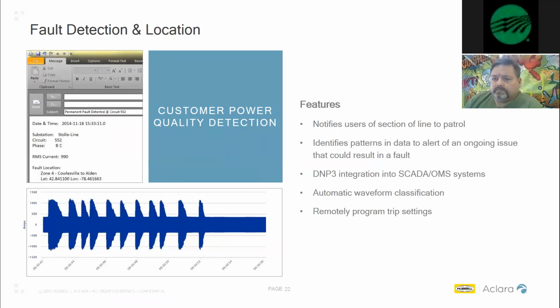Fault detection and location. Okay, so this is a really important one for me to go through with you. Using the sensors that are installed throughout your network, you obviously want to know where faults are occurring, where outages are occurring, and how do I do that? How does the system help me do that without manually driving a truck and having to patrol these lines manually? The Aclara grid monitoring system uses 2 different ways to detect these types of faults. We use a circuit segmentation method, which, as you can figure out pretty simply, means that if you're installing on a feeder, you have 3 sets of sensors. When those sensors are involved in a certain event or a disturbance or an outage condition, each one of those sensors will detect if it sees any kind of anomaly on that line, and we send that back. So you can then segment where you're going to send the patrol to figure out where that actual outage or fault is, based on whether it passed through this sensor location or through a downstream sensor location.